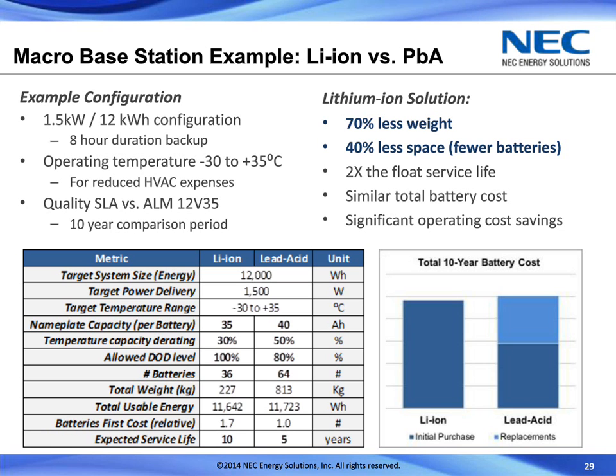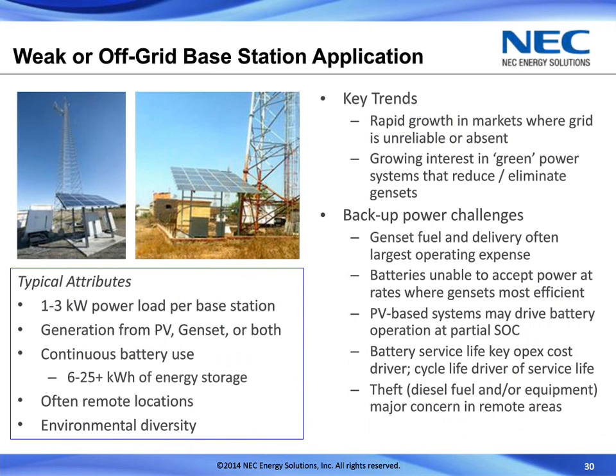Okay, so the next application, weak or off-grid base station. A key trend there, obviously, is we're seeing growth in markets where grid is unreliable or absent, hence the weak or off-grid. Growing interest in green power to reduce or eliminate gensets. And the reason for that is, the first challenge there, genset fuel and delivery is the largest operating expense. Another challenge is the lead acid batteries can't accept those high charge currents, where the diesel gensets are most efficient. And the lithium really can make a difference here.